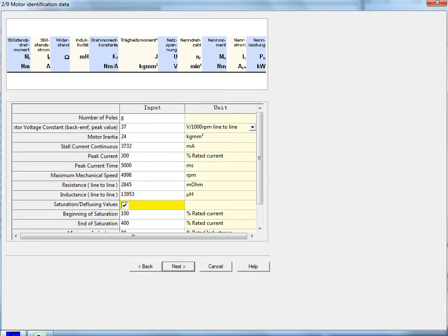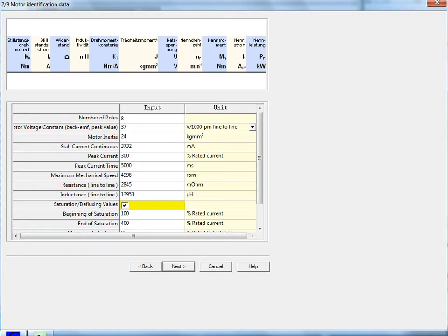On step two, it has the motor's pole count, the motor voltage constant. This says volts per thousand RPM, and it is the peak of the sine wave. Rotary inertia is set in kilogram millimeters squared. The continuous stall current at zero speed is in amps RMS, and is in milliamps. The peak current is set based on a percentage of the rated current, which is at rated speed.